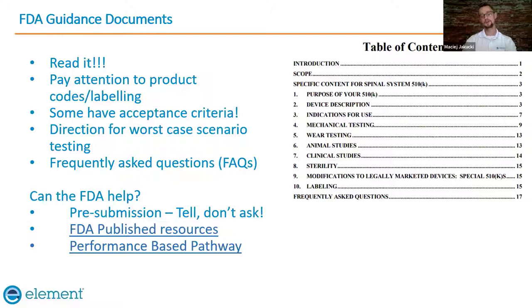The other part is a performance-based pathway approach, where if you have a design like a screw or a plate, something pretty common that doesn't necessarily create a lot of risk, they've actually defined criteria you just need to meet, and you don't need to go through the whole predicate device exercise of comparing to something else on the market. So pay attention to those devices, and always check if those exist, because it can really help you through the process.